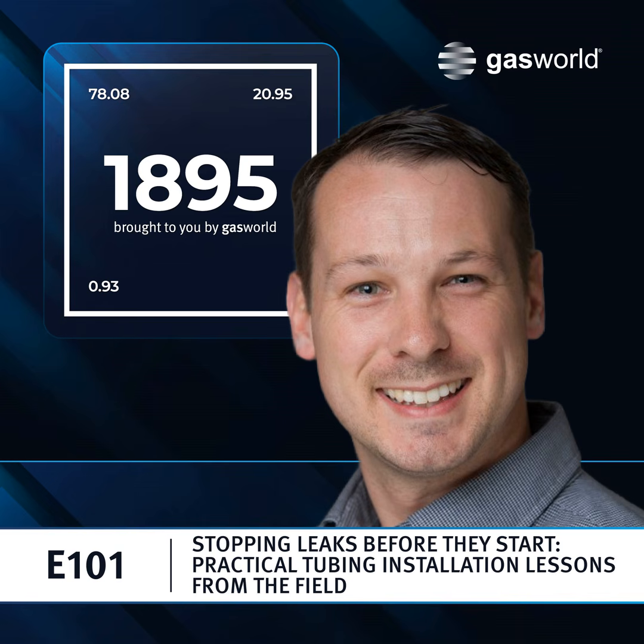So rather than installing everything and then having to go back and check a sampling of, say, 10%, what we'd call intrusive inspection, which would be opening up those fittings and checking for clearances and proper pull-up, all those types of things, one of the things that you can do is an in-process inspection, which as you're pulling up the fittings, you're doing more detailed inspection throughout, but it doesn't require then an intrusive sampling inspection later on.